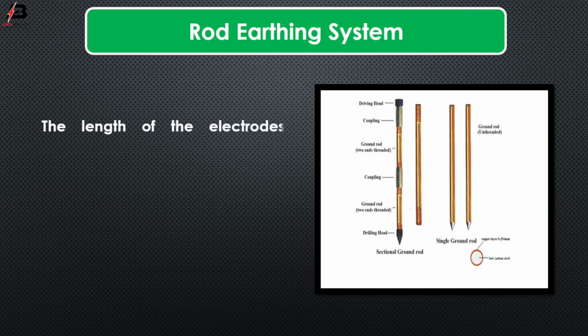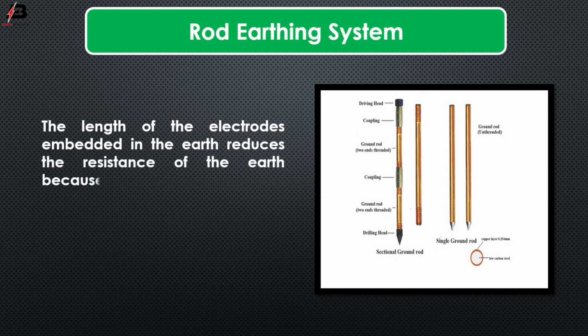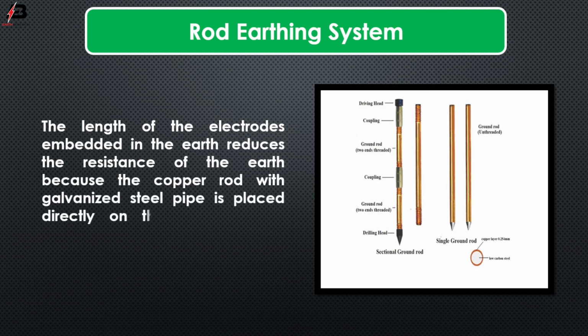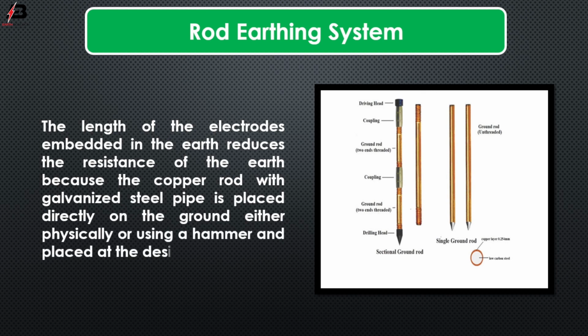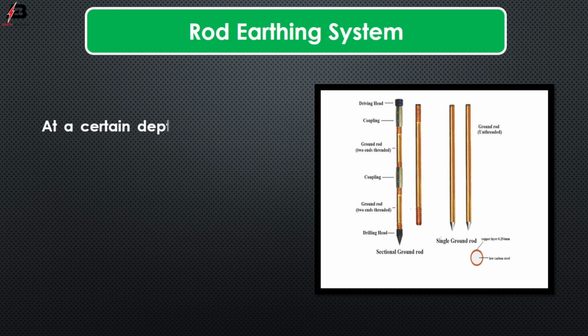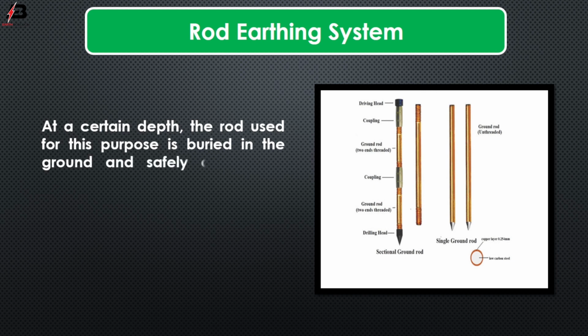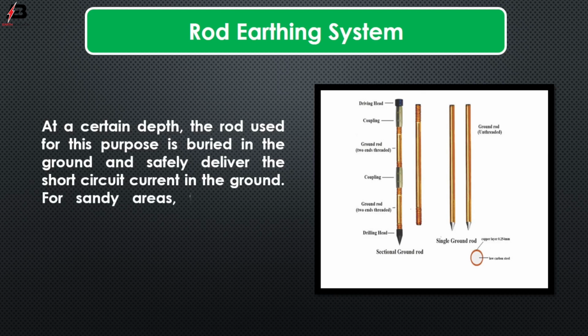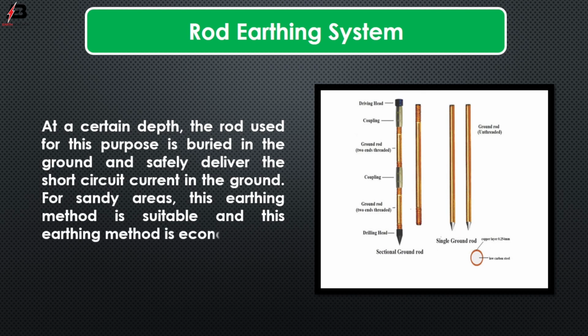Rod earthing system. The length of the electrode embedded in the earth reduces the resistance of the earth because the copper rod with galvanized steel pipe is placed directly on the ground, either physically or using a hammer, and placed at the desired value. At a certain depth, the rod used for this purpose is buried in the ground and safely delivers the short circuit current into the ground. For sandy areas, this earthing method is suitable and this earthing method is economical.